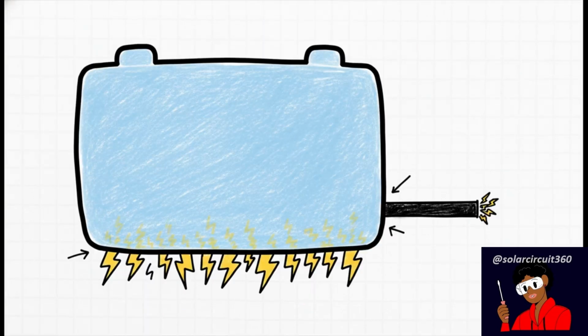Have you ever wondered why a fully charged system suddenly trips or overheats right when you need it most? Well, the root cause of all this heartache is something we call the capacity mistake. This happens when people spend an absolute fortune on energy storage. They calculate exactly how many kilowatt hours they need to run their cabin or their backup power, but they completely ignore the massive electrical current flowing through their system. It's like building a giant water tower but hooking it up to a tiny garden hose. They design a system based entirely on how much energy is in the tank, without ever stopping to ask how fast that energy actually needs to squeeze through the pipes.